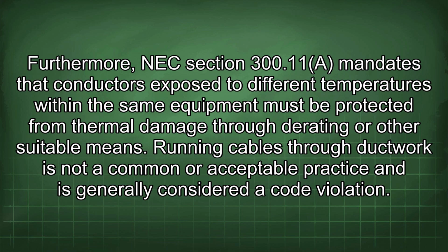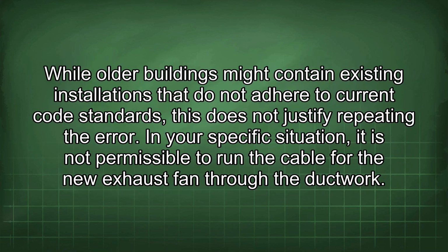Running cables through ductwork is not a common or acceptable practice and is generally considered a code violation. While older buildings might contain existing installations that do not adhere to current code standards, this does not justify repeating the error.